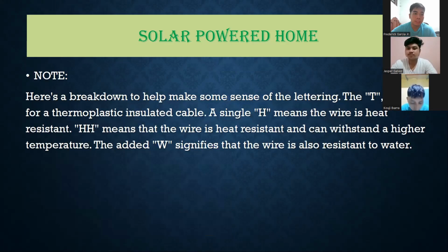Now, note, here's a breakdown to help make some sense of the lettering. The T stands for thermoplastic insulated cable. A single H in the wire means it's heat resistant. Double H means that the wire is heat resistant and can withstand a higher temperature. The added W signifies that the wire is also resistant to water.